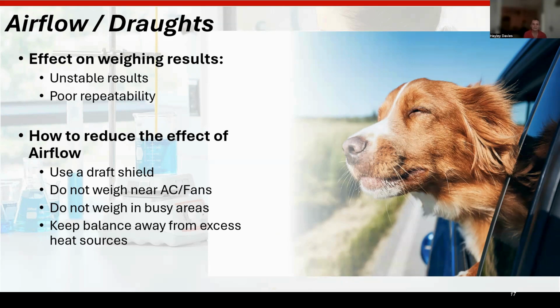To reduce the effect of airflow, use a draft shield when weighing. Don't weigh near air conditioning, fans, or open windows, and avoid busy areas with a lot of foot traffic or doors opening and closing. Keep the balance away from excess heat sources too, such as near a window on a hot day, which will heat up the balance and affect the weighing.